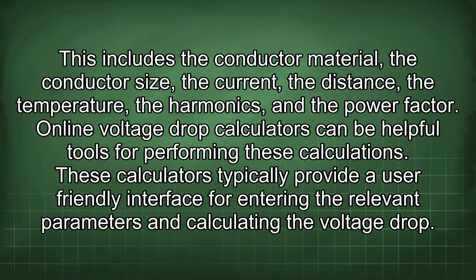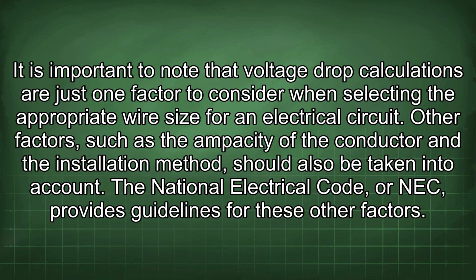Online voltage drop calculators can be helpful tools for performing these calculations. These calculators typically provide a user-friendly interface for entering the relevant parameters and calculating the voltage drop. It is important to note that voltage drop calculations are just one factor to consider when selecting the appropriate wire size for an electrical circuit. Other factors, such as the ampacity of the conductor and the installation method, should also be taken into account. The National Electrical Code, or NEC, provides guidelines for these other factors.